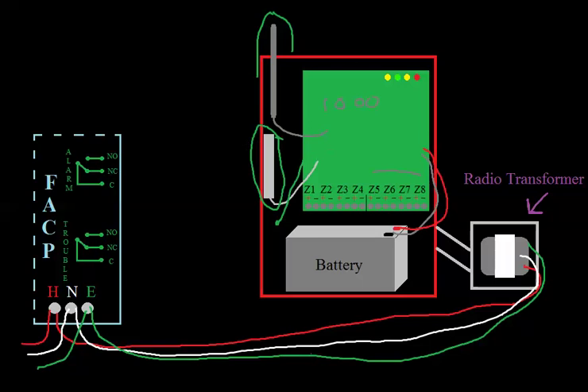But anyway, so let's look at our zones. Let's say we take alarm for zone one. And we go to our alarm contacts, just like we did on our dialer. And then we're going to go to common and we're going to put our resistor on there. Now this resistor, this is something I didn't really mention much when I did the dialer, but it's the same principle here. If this circuit opens up here, if this radio circuit opens up, is your fire alarm panel going to go into trouble? I mean, there's a resistor here, it's being supervised. Well, no, it's not because the fire alarm panel doesn't monitor its own alarm contacts.